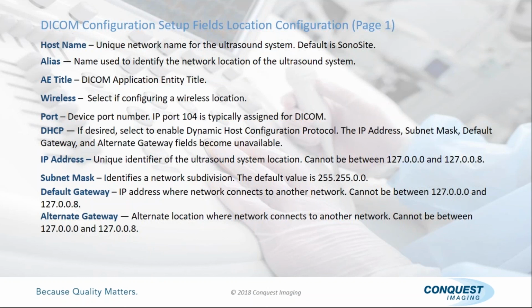Subnet mask 255.255. This one says 0.0, and the reason it says that is because, for whatever reason, Sonosite, yes, NerveBlock specifically I know of, and the Micromax set it up as 0.0, which is very unique. Normally they're 255.255.255, which limits your network size to 254 devices. This does not limit it to 254. This network, the 255.255, can have over 60,000 devices on it, which is why I don't understand why they default to this.